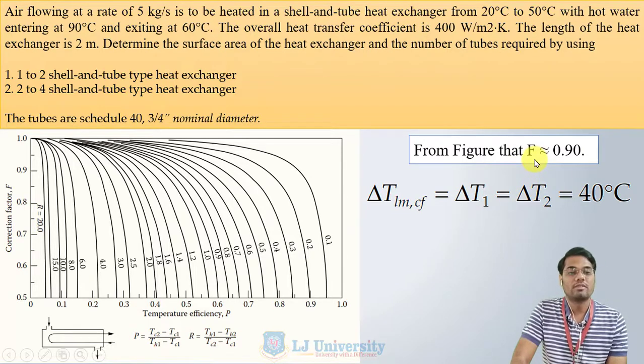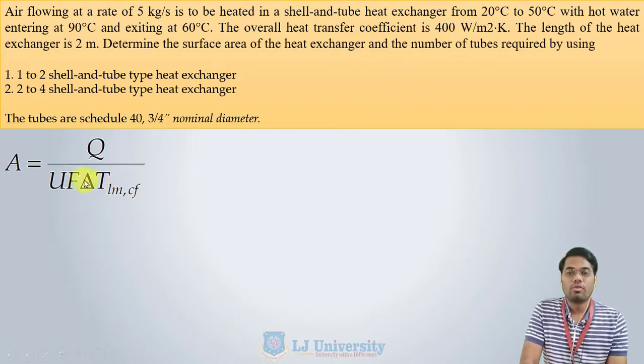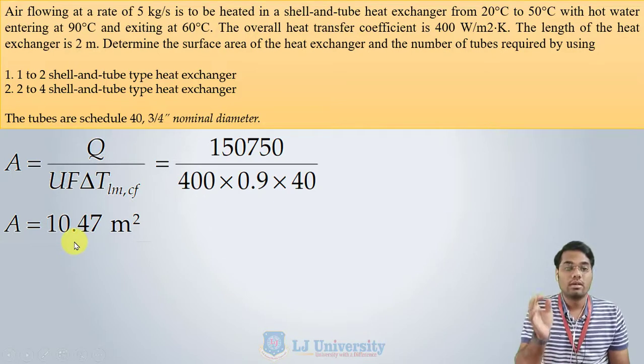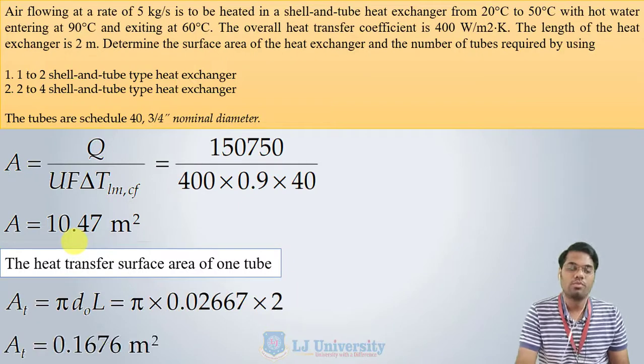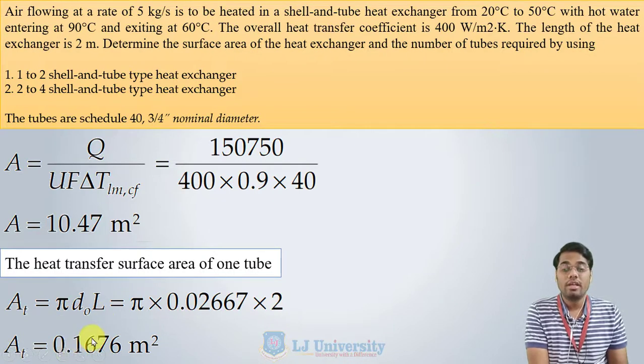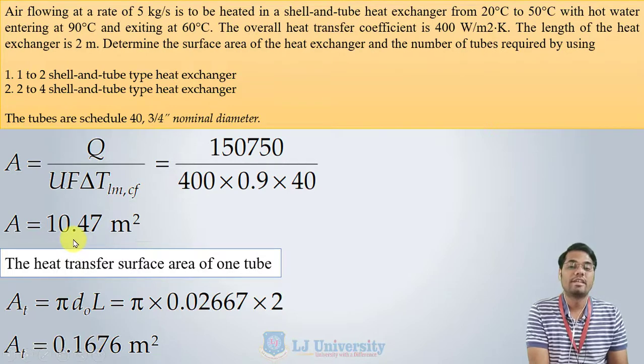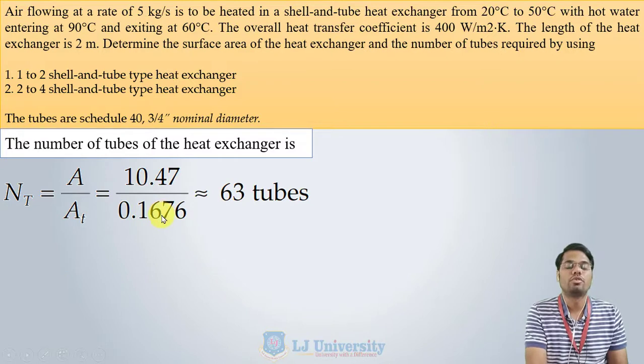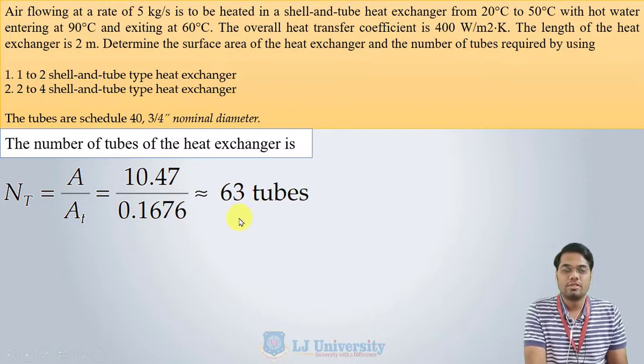With ΔT = 40°C, F = 0.9, known Q, and U = 400 W/m²K, the required area is A = 10.47 m². The heat transfer surface area for one tube is calculated as π·d·L, with diameter 0.02667 m and length 2 m, giving approximately 0.16 m² per tube. Dividing total area by area per tube: 10.47 / 0.16 = 63 tubes required.